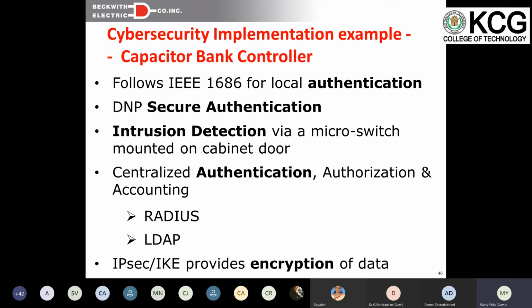As a result, you get the IEEE 1686 standard for authentication, and we added secure DNP. Intrusion detection: if somebody opens the door of a cabinet, SCADA automatically gets information saying that somebody intruded. And then you have centralized authentication, authorization, and accounting. That means if you have passwords on 3,000 devices, it's very difficult to drive to each place to change passwords.